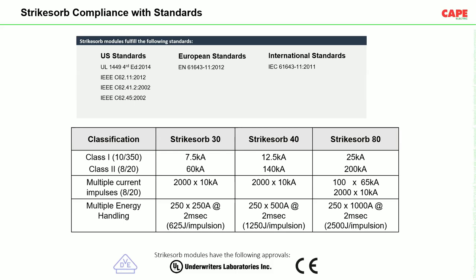In real life, lightning can be multiple and it can be back to back. Let's say there can be back to back 10 lightning strikes or 10 subsequent impulses. For that, we have tested our bus bar mounted SPDs with 2000 back-to-back strikes of 10 kiloamperes, and Strikesorb 80 specially tested with 100 back-to-back strikes of 65 kiloamperes each. Also, we have tested our SPDs with long duration impulses, like 250 impulses of 250 amperes, 2 millisecond. All three SPDs have been tested with these impulses.